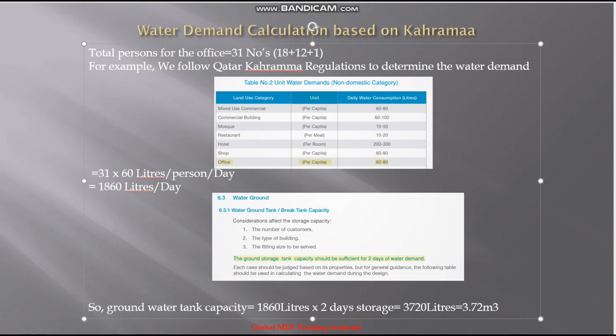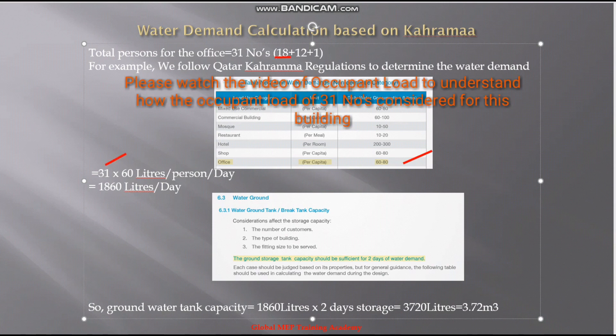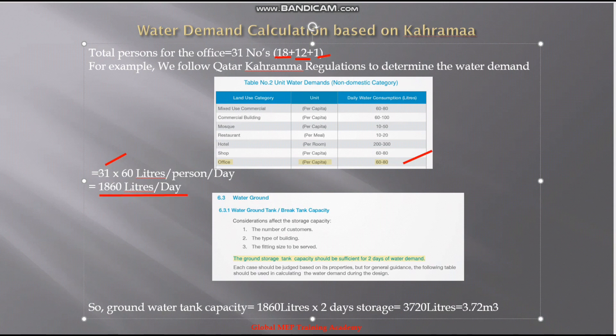Now we apply the Qatar Kahramaa regulation to size the tank. The daily water consumption for the office building is 60 to 80 liters per person. We have 31 people total: 18 permanent staff, 12 temporary visitors and office room occupants, and 1 receptionist. This gives us 1,860 liters per day. The ground water tank must have a minimum two days storage capacity, so: 1,860 liters × 2 days = 3,720 liters, which equals 3.72 cubic meters. This is the required capacity for the ground storage tank.